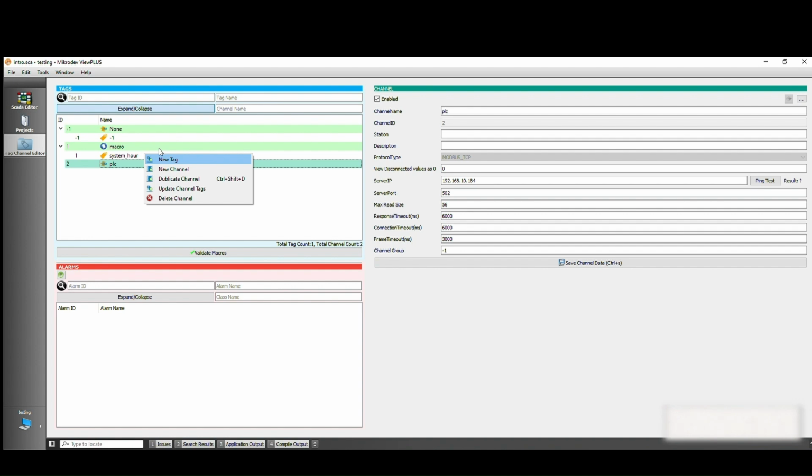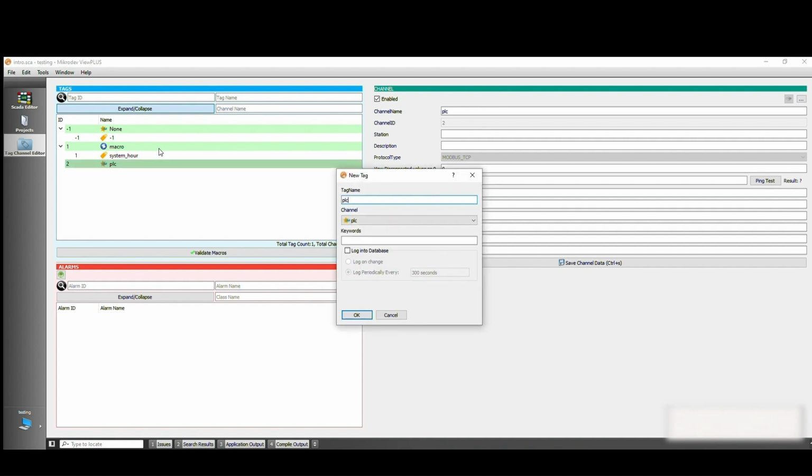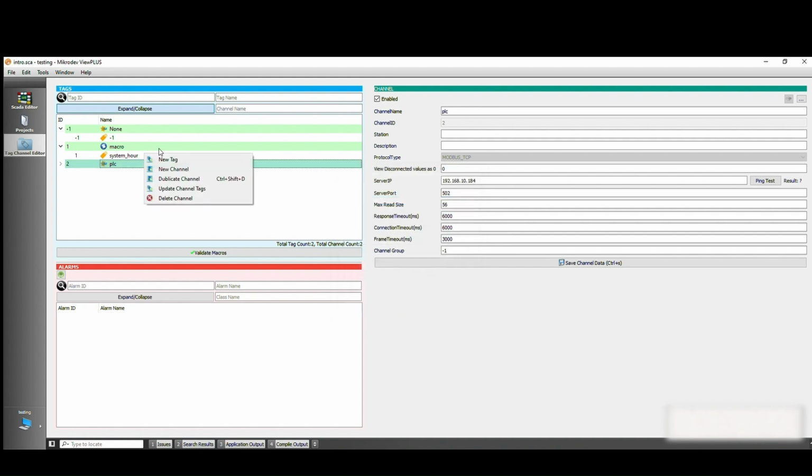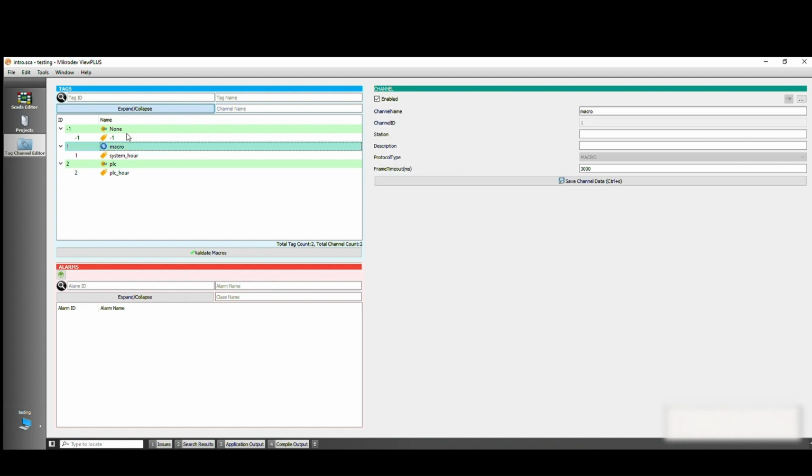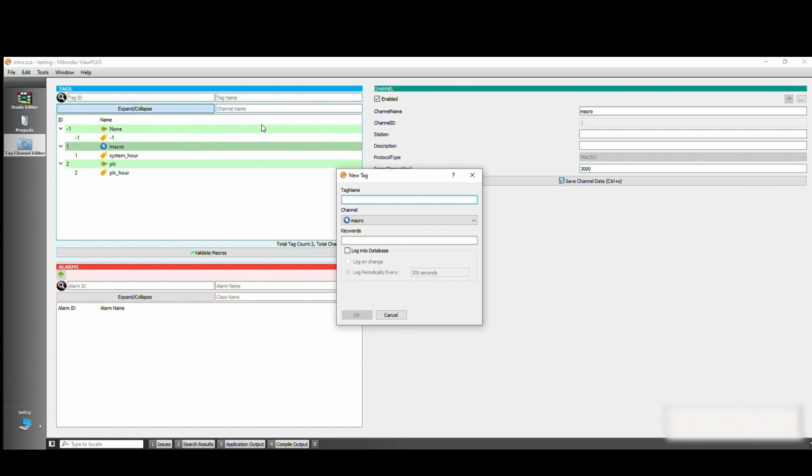To retrieve the time information from the Mikrodev PLC, select the variable address as 18016 and the variable type as inverse U32 under the Modbus tag. Due to the GMT expression, we need to subtract 10,800 seconds from the read Modbus address.